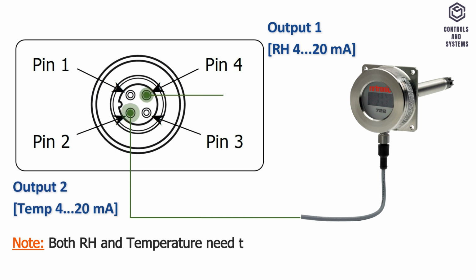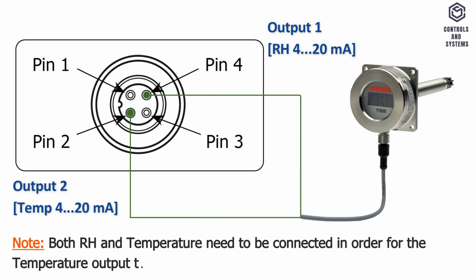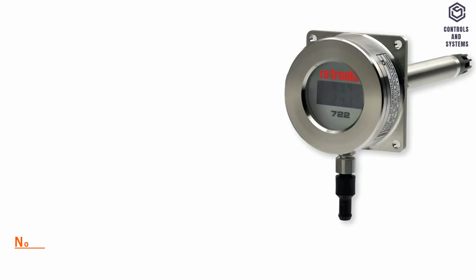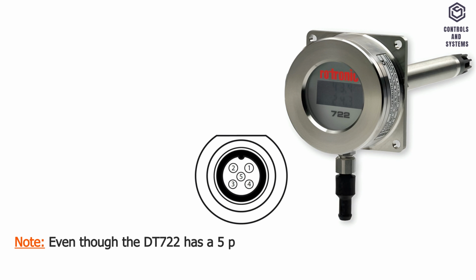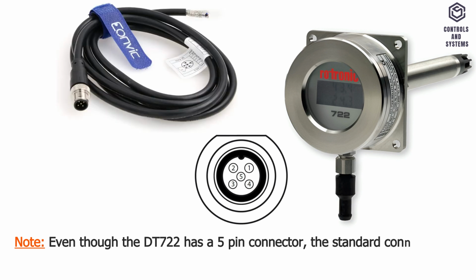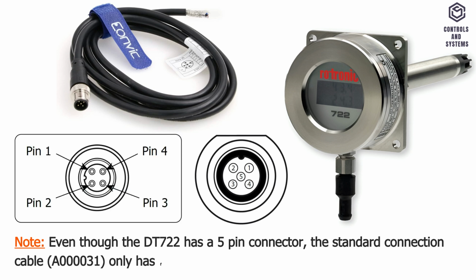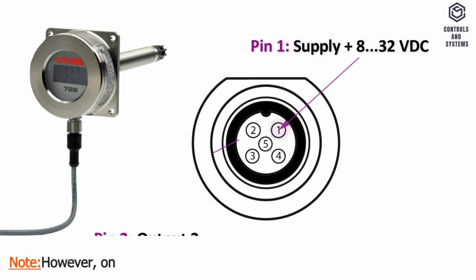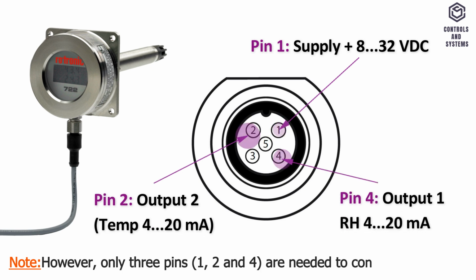Both RH and temperature need to be connected in order for the temperature output to work. Note: even though the DT722 has a 5-pin connector, the standard connection cable only has 4 pins or wires. However, only 3 pins, 1, 2 and 4, are needed to connect the DT722.